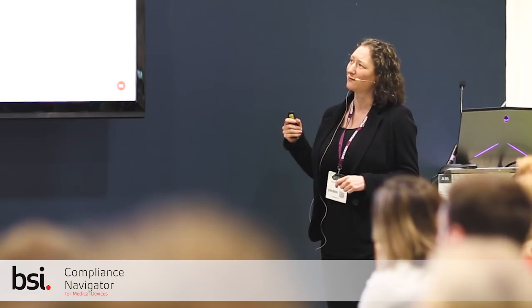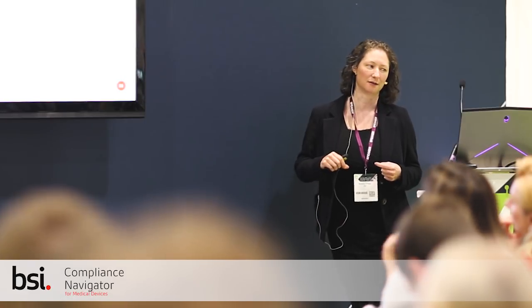The significant difference in equivalence under the MDR is that for class 3 devices and for implants, equivalence can only be claimed with the manufacturer's own device. And these are words out of the MDR. So you can only claim equivalence to your own devices or devices where the other manufacturer has a contract with you allowing you full access to all of the information on that device on an ongoing basis. And then for those other devices, not the class 3 or the implants or those other high-risk devices, it says only sufficient level of access.